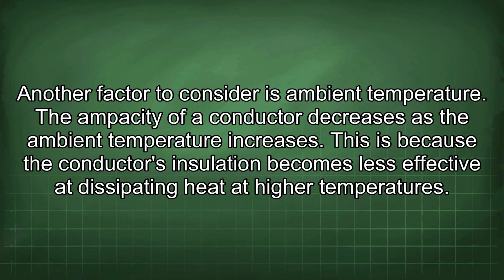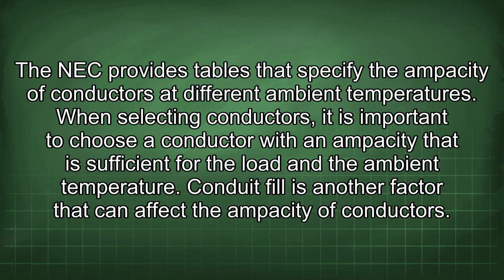The ampacity of a conductor decreases as the ambient temperature increases. This is because the conductor's insulation becomes less effective at dissipating heat at higher temperatures. The NEC provides tables that specify the ampacity of conductors at different ambient temperatures. When selecting conductors, it is important to choose a conductor with an ampacity that is sufficient for the load and the ambient temperature. Conduit fill is another factor that can affect the ampacity of conductors.